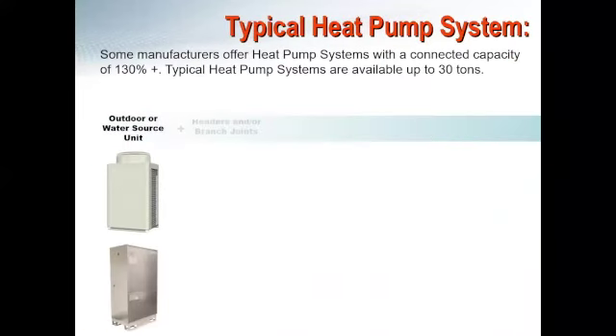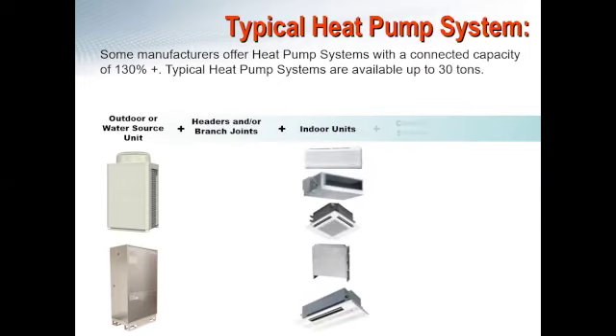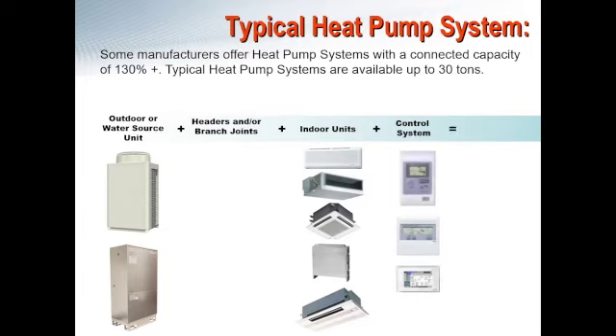So just quickly, we're going to look at the different types of equipment used for the 2-pipe heat pump system. We're going to start from the left, moving on over to the right. It's actually a very simple system. So you're going to have your compressorized condensing unit. Now that unit can either be an air source condensing unit, like we're going to see here on the top. That unit is going to typically be placed outside, although that is not always the case. We leave out pictures of your headers and branches and joints because that's really just going to be your flexible refrigerant line set. And then you're going to have an indoor unit.